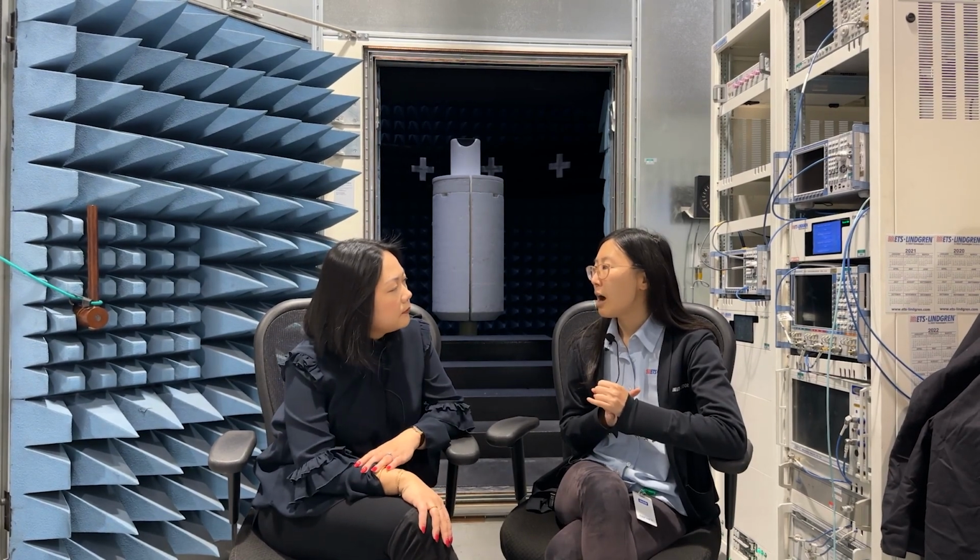So I can select the test case, and I have the test instruments that are connected to the chamber. We support a wide range of test instruments, like 5G communication testers or Wi-Fi communication testers, Bluetooth, UWB, and spectrum analyzers, signal generators, VNA, power meter, etc. There are a lot of testers we support, from basically the major vendors. So it's very easy to pick. If you have a tester, likely we support that. MQuest controls the instrument.